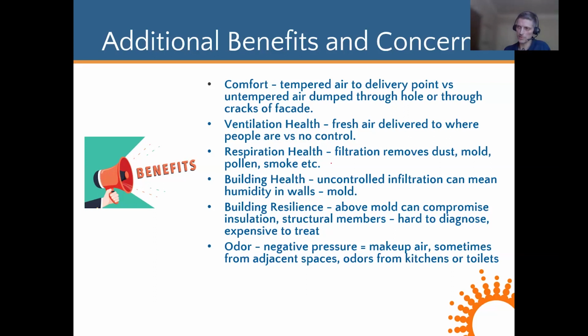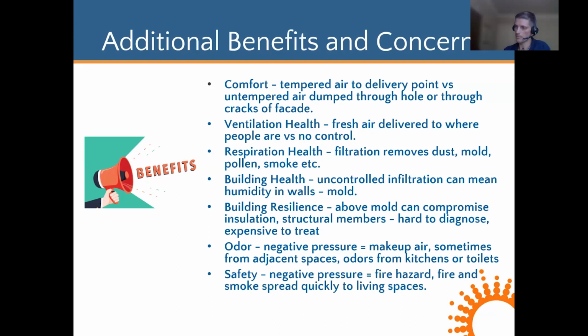Odor can be an issue with a negative pressure created by an exhaust-only scenario. We talked about that. Makeup air can come from various sources and sometimes bring odors from adjacent spaces. And it can potentially be a fire hazard, allowing fire and smoke to spread more quickly.